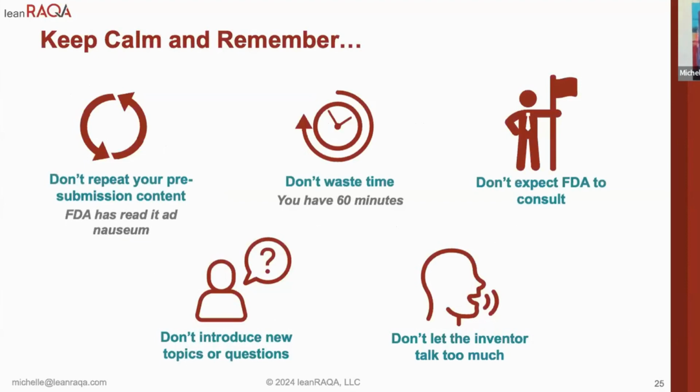So it's important to remember, if you are having a meeting, do not repeat your PRESUB content. Everybody has read your PRESUB ad nauseum at this point, and you are going to waste your time if you try to give any background or context that had already been discussed in your pre-submission. Don't expect FDA to consult on your pre-submission. They will not tell you what to do or necessarily tell you their opinions that are not directly related to the topics under discussion.